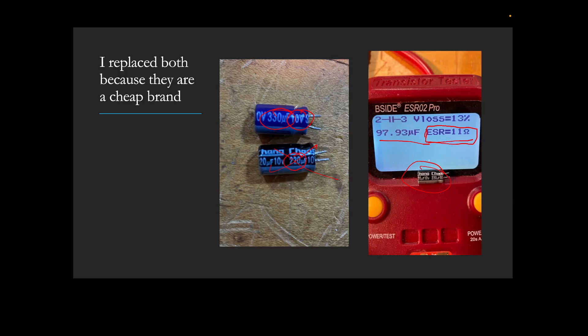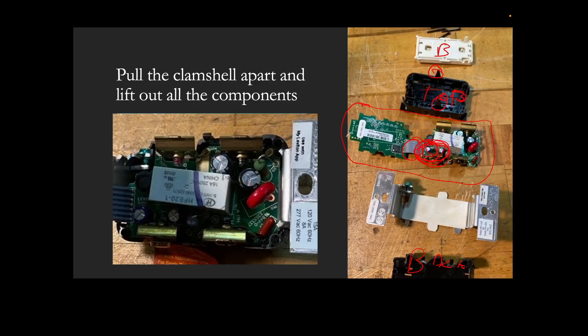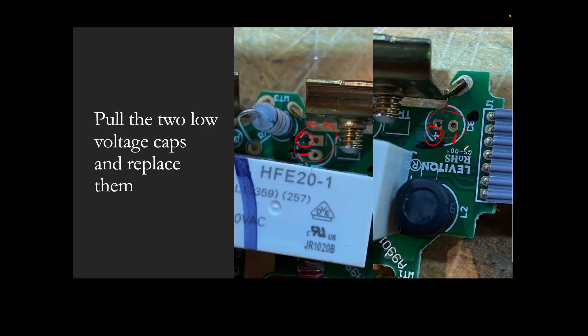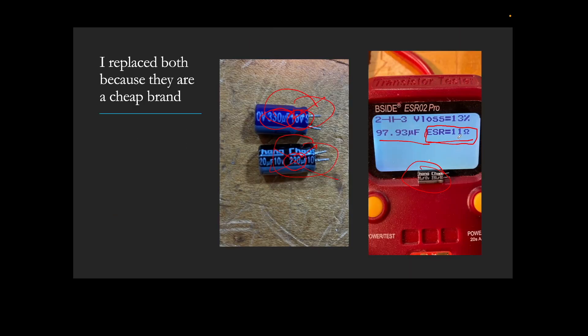Even though this capacitor measured as good, I went ahead and replaced both of them. These are not good quality capacitors. Caps, just like batteries, can go bad over time, especially the really cheap ones. So I just pulled both of these out. I did check the other high voltage capacitors in this device, you can see those over here. Those are high voltage capacitors, and I left those alone. They seem to be just fine.